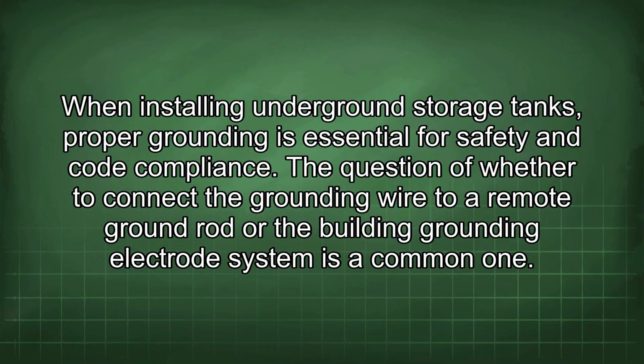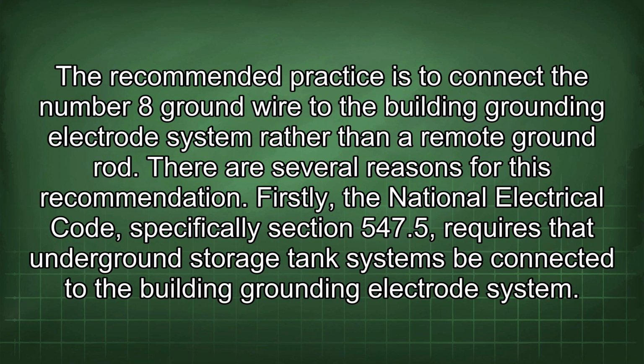When installing underground storage tanks, proper grounding is essential for safety and code compliance. The question of whether to connect the grounding wire to a remote ground rod or the building grounding electrode system is a common one. The recommended practice is to connect the number 8 ground wire to the building grounding electrode system rather than a remote ground rod. There are several reasons for this recommendation.